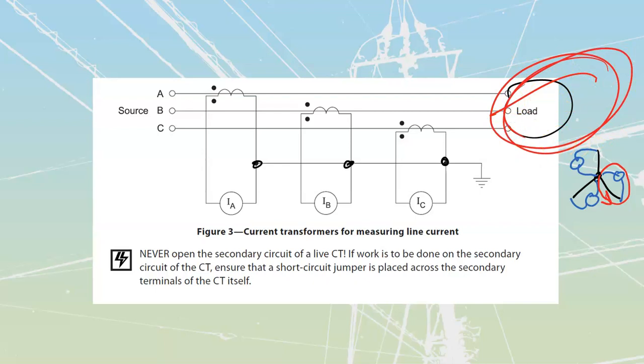There's a big important note here. We've iterated this in second year, first year, third year, fourth year, and we're going to keep talking about it until you're a journeyperson because it's so critical: never open the secondary of a CT. If you open the secondary of a CT, you're going to drive it hard into saturation, then really quickly drop it back through in the opposite direction, which induces a very large voltage across it. Really dangerous - we don't want to see that.